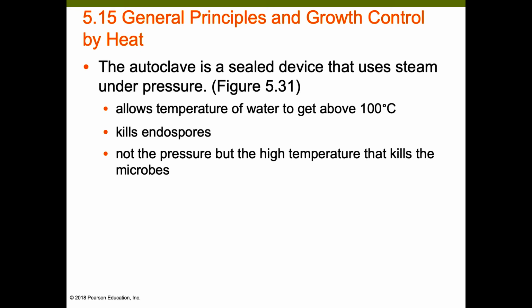And it has high pressure. And so that high pressure with that steam at 121 is enough to kill endospores. And so what we do as microbiologists who are dependent on autoclaves is we actually will put spores in the autoclave. We will run the autoclave and see if we can regrow the spores. If we can regrow the spores, that's a problem, and we need to get our autoclave fixed. So we test it with spores to make sure that the autoclave is working.